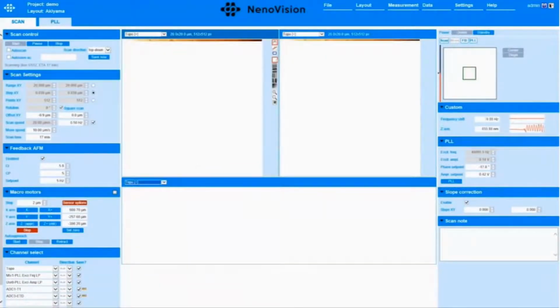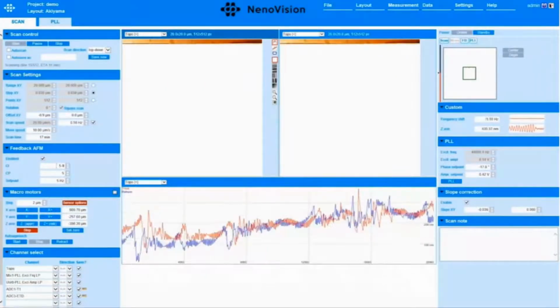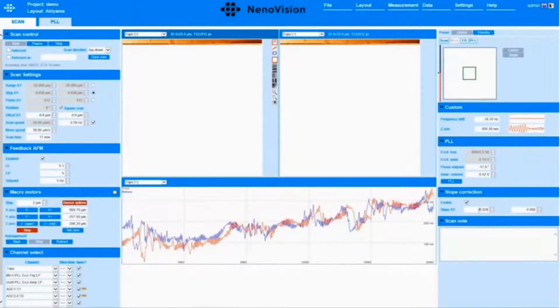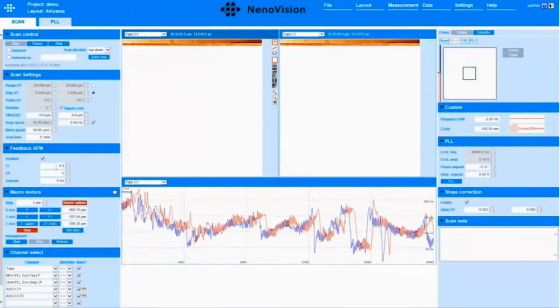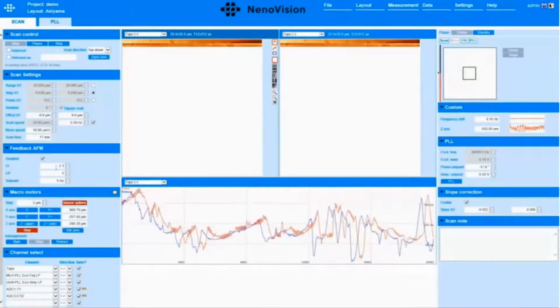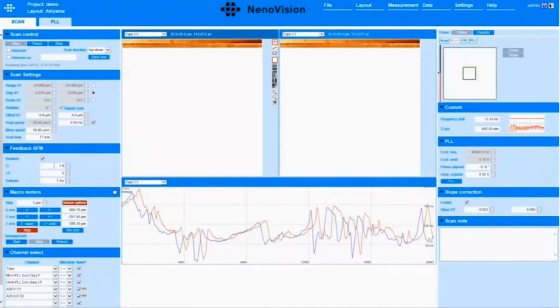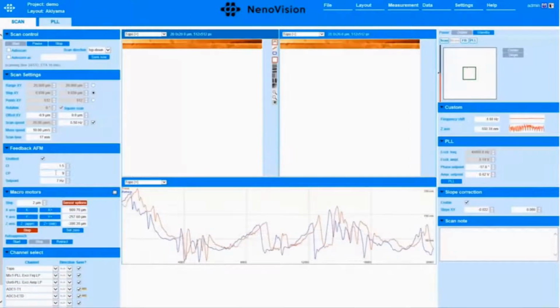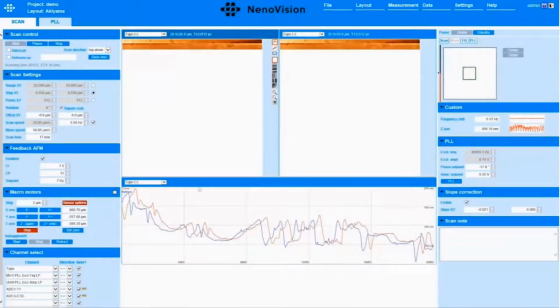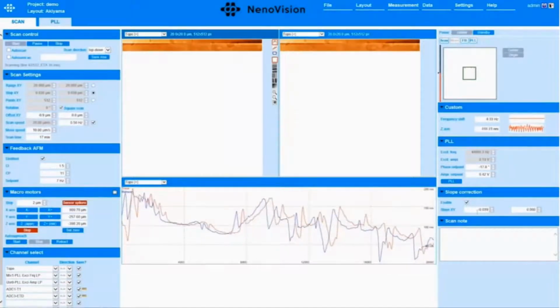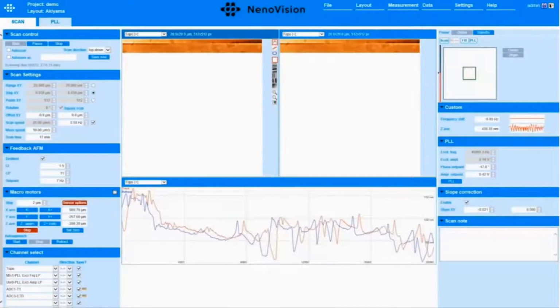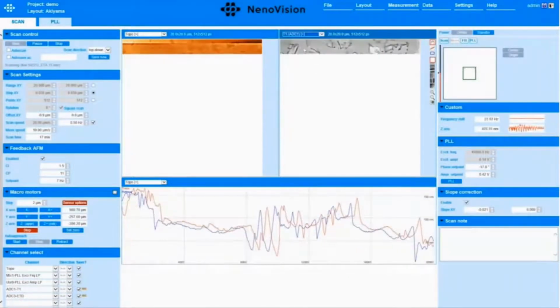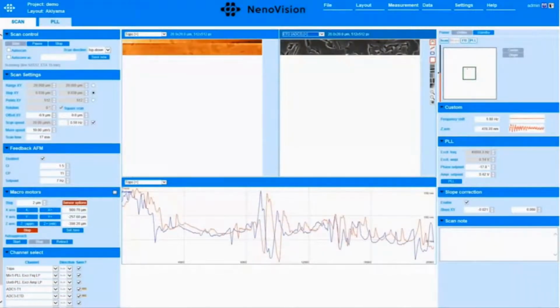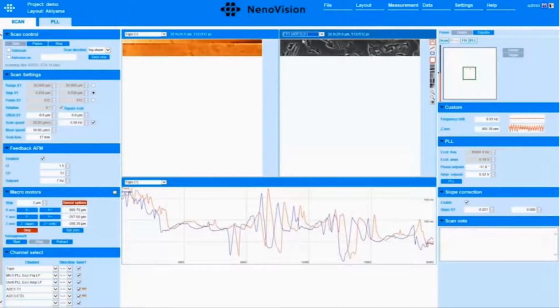First, we need to adjust the parameters. We will measure a few lines and correct especially the slope. You can see it in the graph that the slope is changing. And we need to lower the integral parameter because there is a lot of noise in the graph. Also, we raise the set point. You can see it in the left in the feedback AFM box. And we push a little bit more to the surface. Now we check the SEM channels, secondary electrons and backscattered electrons, if the sample is properly focused before we start the measuring again.